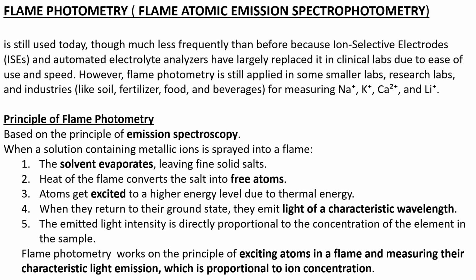The principle of flame photometry is emission spectroscopy. In this, a solution or sample that contains metallic ions is sprayed into the flame. First, the sample goes through a nebulizer and it is then sprayed into the flame. The solvent will evaporate and the fine solid salt will remain. The heat of the flame converts this salt into free atoms. The atoms get excited to a higher energy level due to the thermal energy of the flame. When they return to the ground state, they emit light of a characteristic wavelength. The emitted light intensity is directly proportional to the concentration of the element in the sample.